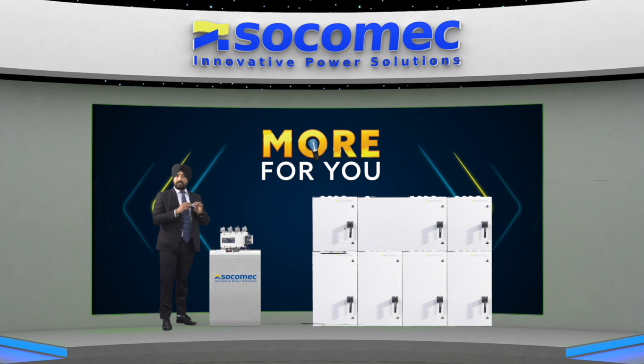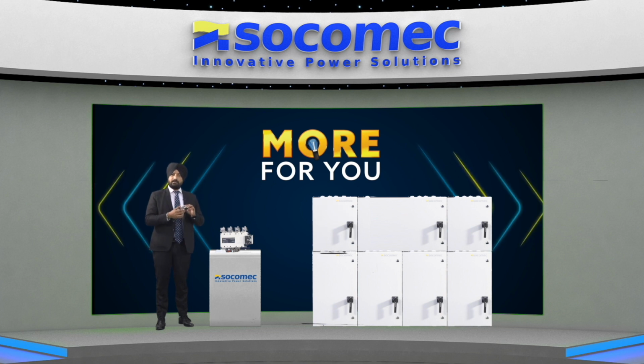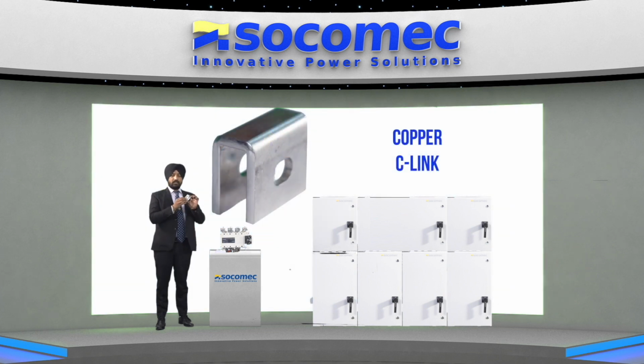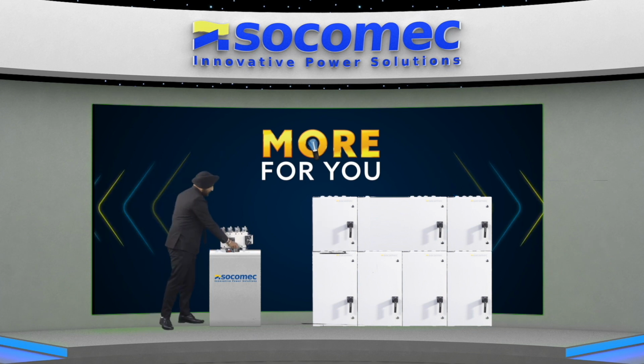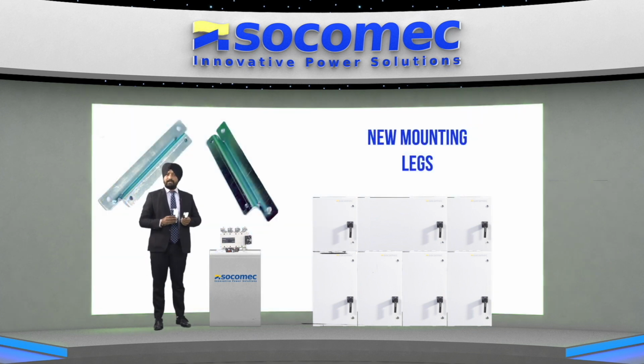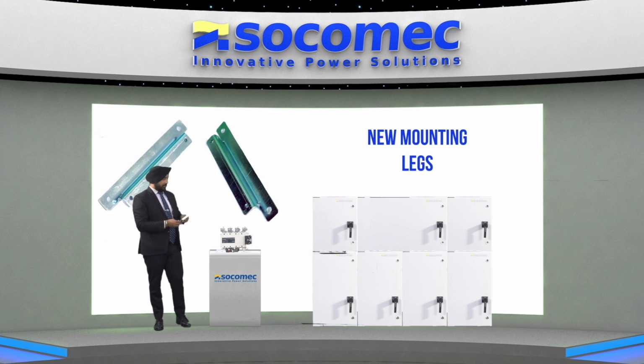Since this product's dimensions are slightly different, a copper C-link is available to make it fit comfortably into the existing bus bar fitment. This copper C-link will help align my bus bar into the same alignment already available on site. It will also require replacing the mounting legs, because the new product in this SIRCOVER range comes with its own mounting leg, so you need to use the mounting legs inside this retrofit kit to match the dimension of the bus bar termination.